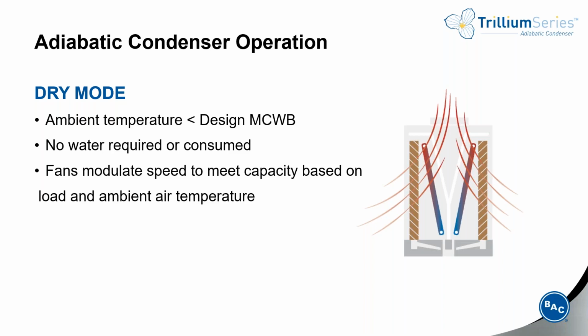This is when ambient temperatures are below the designated wet mode switch point. This switch point is field adjustable, but BAC recommends using the mean coincident wet bulb associated with your design day conditions. So when ambient temperatures are below this mean coincident wet bulb temperature, your unit operates essentially as an air-cooled condenser. No water is used. The variable speed fans will modulate to meet capacity based on the load and the ambient air conditions.